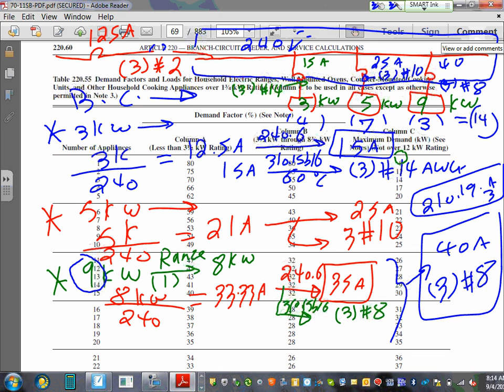For branch circuits, nameplate value. We use the 3 kW like you saw here for all these 4, the 5 kW for all these 7 branch circuits. For the ranges, only if it's a range. If the 9 kW one was an oven, you can't do this. So only if it's a range. That's why I wrote range here. That's the exception for ranges. If it's a range, then you're allowed to use a table.